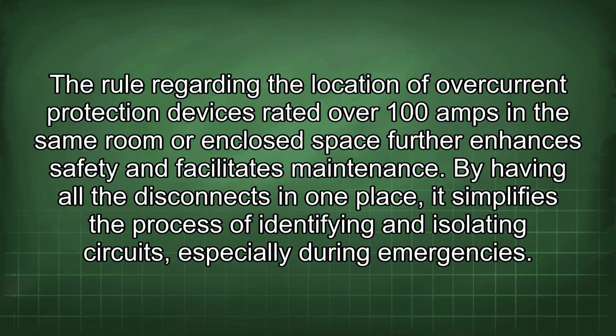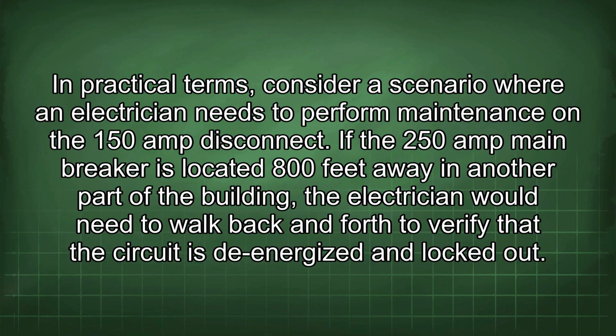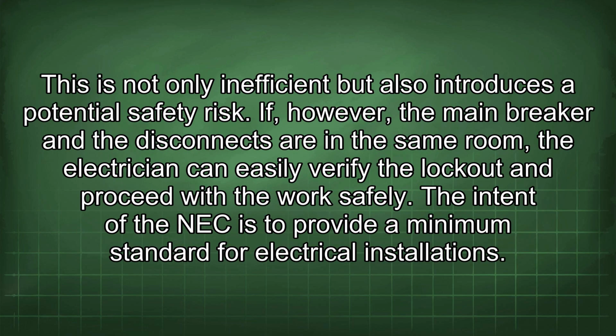The rule regarding the location of overcurrent protection devices rated over 100 amps in the same room or enclosed space further enhances safety and facilitates maintenance. By having all the disconnects in one place, it simplifies the process of identifying and isolating circuits, especially during emergencies. In practical terms, consider a scenario where an electrician needs to perform maintenance on the 150 amp disconnect. If the 250 amp main breaker is located 800 feet away in another part of the building, the electrician would need to walk back and forth to verify that the circuit is de-energized and locked out. This is not only inefficient but also introduces a potential safety risk. If, however, the main breaker and the disconnects are in the same room, the electrician can easily verify the lockout and proceed with the work safely.